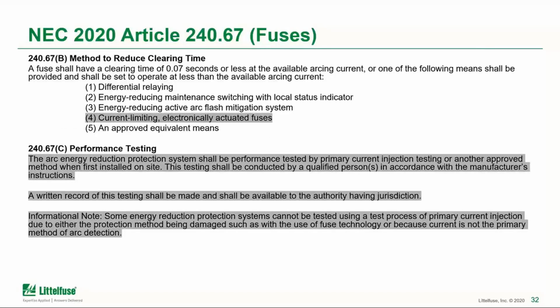of arc mitigation. So here under 240.67(B), the list is a little smaller, but it talks about differential relaying, energy reduced maintenance switches, energy reducing arc flash mitigation systems or relays, current limiting electronically actuated fuses, or an approved equivalent means approved by the AHJ. So this is something that has also been added so that the circuit breakers and the fusing were given the same treatment in terms of limiting arc mitigation.